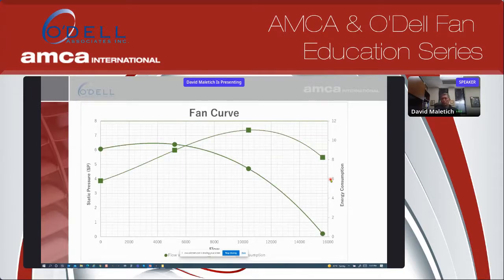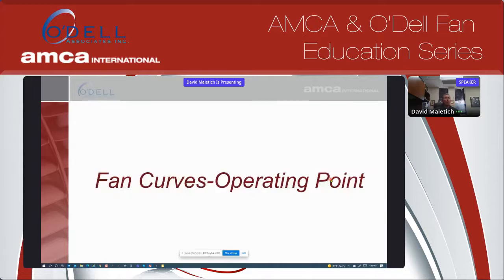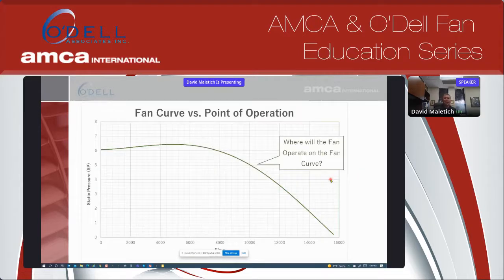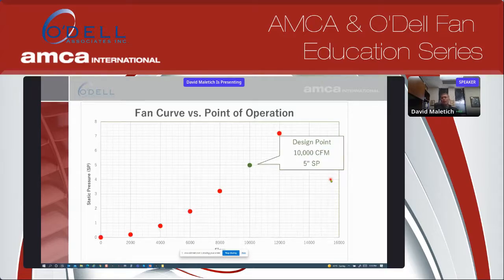In this case, we've only used 4 points to create a curve. The more points you use, the more accurate the curve is. Most fan manufacturers typically use between 8 to 12 points in order to generate a fan curve. A lot of times people come to us and say, hey, I've got a fan curve here. Where is my system going to operate on this fan curve? From a fan manufacturer's point of view, the fan can operate at any point along that curve. There's nothing that's going to govern where the fan's going to operate except the system. So when a customer comes to us and says, hey, I need 10,000 CFM and I'm going to generate 5 inches of resistance, what they're really saying is that they have a point out of many points that forms a system curve.